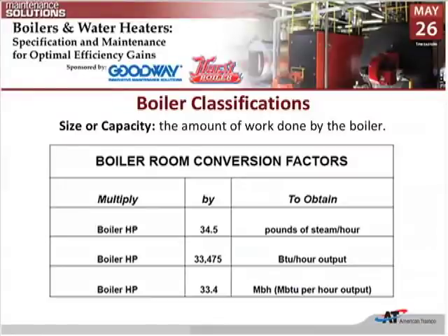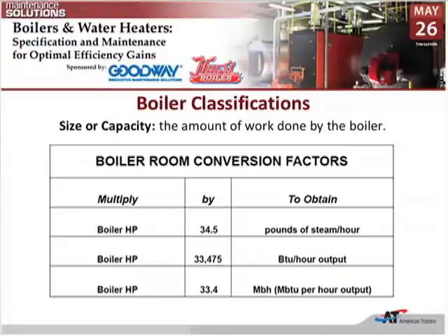Most end users and equipment owners get caught up in combustion efficiency. That is one type — it refers to the characteristics or the flame propagation that occurs based on my fuel and my air. Whenever I look at combustion efficiency, one thing I have to be really concerned about is controlling what my stack temperatures are as they leave the boiler, because the lower my stack temperatures are, the higher my efficiencies will calculate out to be.